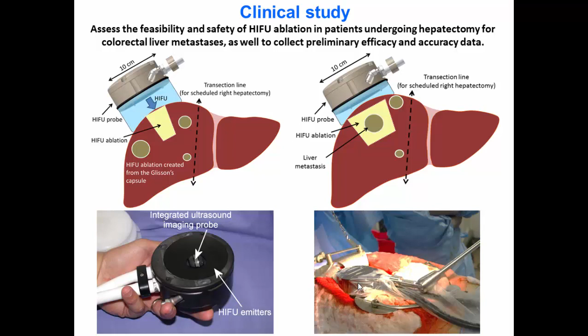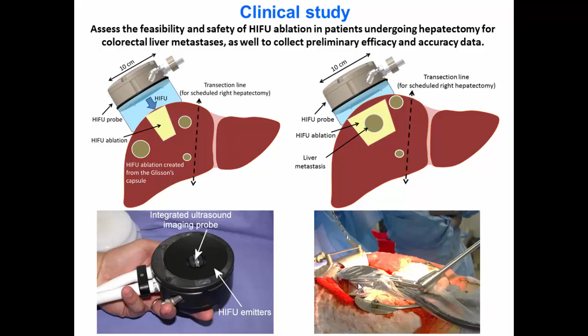This is the probe that has been designed for this clinical trial. The probe can be used by hand by the surgeon, and you can see that it's placed directly in contact with the liver if the ablation lasts less than 1 minute. And if the lesion is planned to be created in 2 minutes, then the probe is fixed on a mechanical arm and also placed directly in contact with the liver.